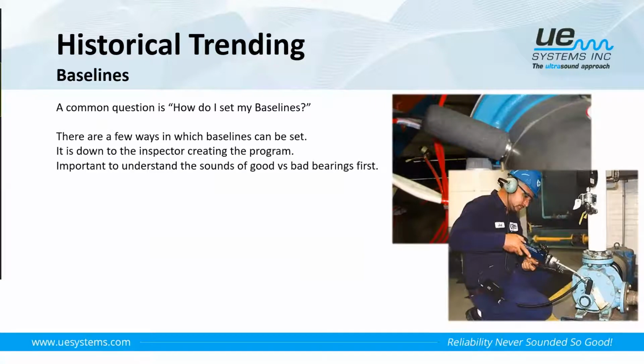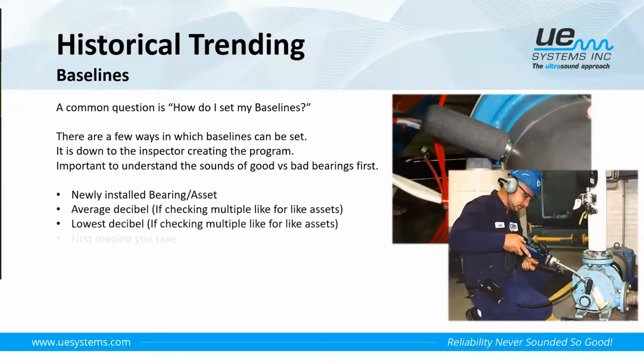So one of the most common questions that we get asked when we're looking at the historical trending method is, how do I set my baselines? Well, there are a few ways in which baselines can be set. It is very much up to the inspector creating the program as to how they go about understanding what baselines to set. We first need to understand that the important thing is what is a good sound against a bad sound. And as we've been discussing, it's that smooth, uniform sound that we want to hear. And we can use a troubleshooting method or a comparative method to help us understand if it is good or not so good. So in an ideal setting, a newly installed bearing on an asset would be our go-to baseline.